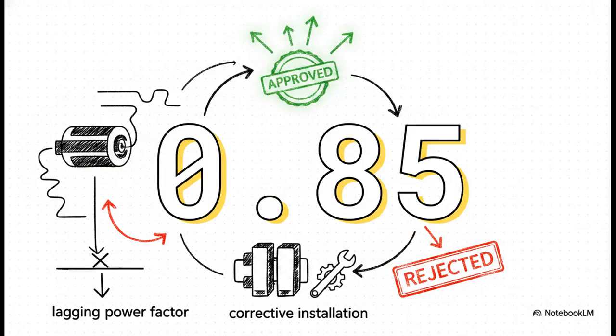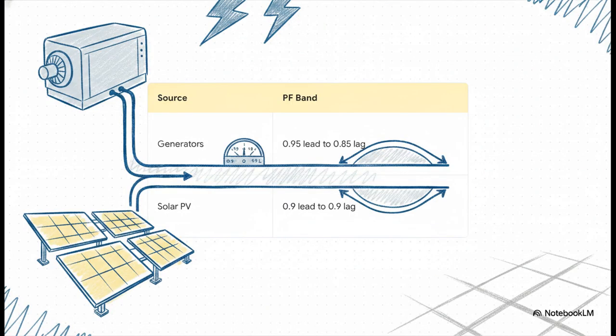Let's start with power factor. For high-voltage consumers, you absolutely must maintain a power factor floor no lower than 0.85 lagging. If you drop below that floor, you risk needing to install some seriously expensive corrective capacitor banks. And what's really interesting here is that generators and large solar installations have even tighter specific operating bands. Generators have to maintain 0.95 leading to 0.85 lagging, and massive solar PV systems of 1 megawatt or more are squeezed into a 0.9 leading to lagging band just to maintain that overall grid efficiency.